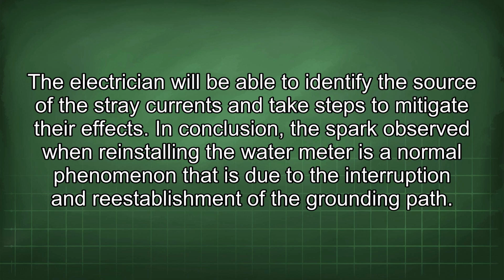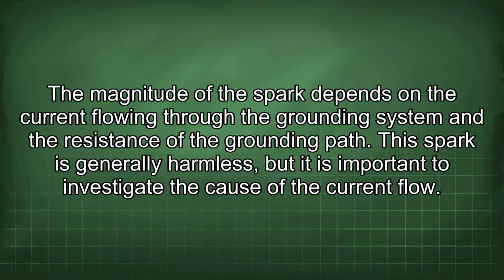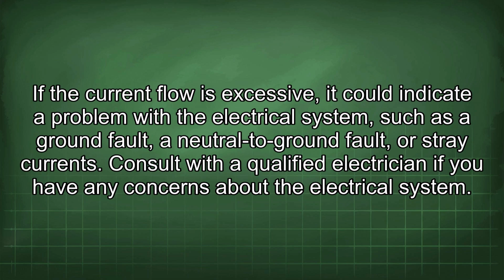In conclusion, the spark observed when reinstalling the water meter is a normal phenomenon that is due to the interruption and re-establishment of the grounding path. The magnitude of the spark depends on the current flowing through the grounding system and the resistance of the grounding path. This spark is generally harmless, but it is important to investigate the cause of the current flow. If the current flow is excessive, it could indicate a problem with the electrical system, such as a ground fault, a neutral to ground fault, or stray currents. Consult with a qualified electrician if you have any concerns about the electrical system.